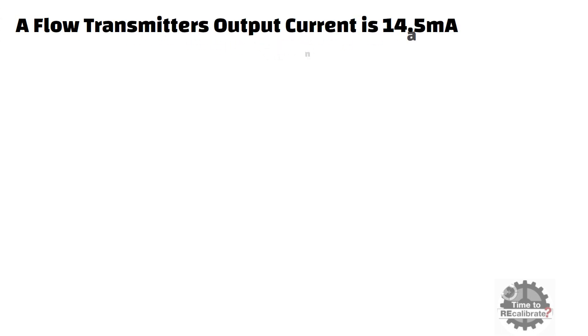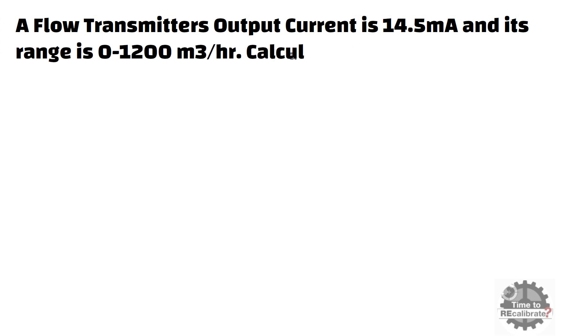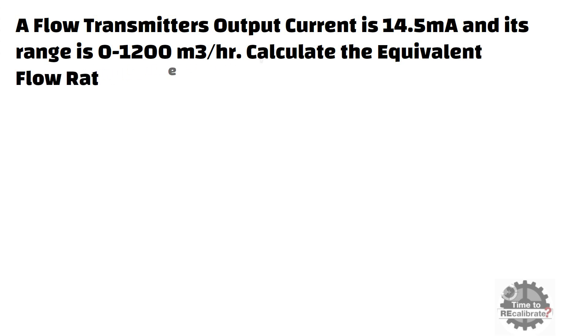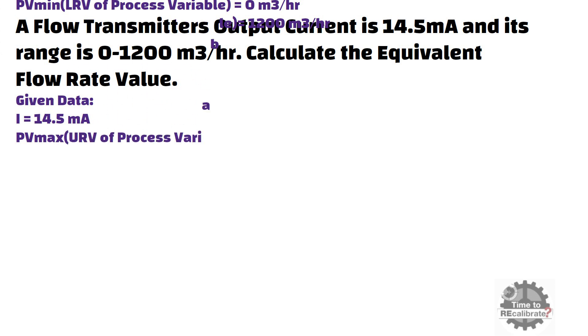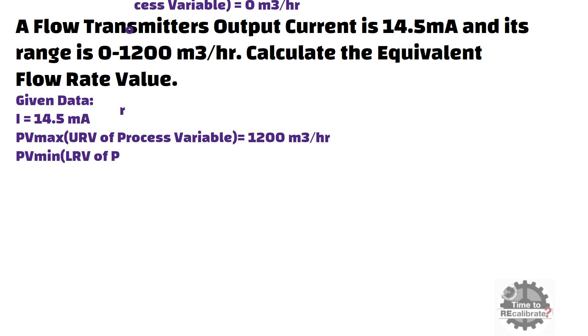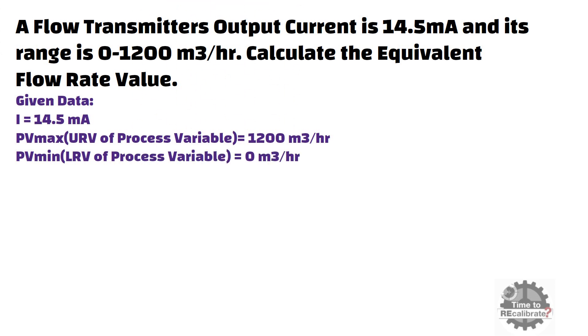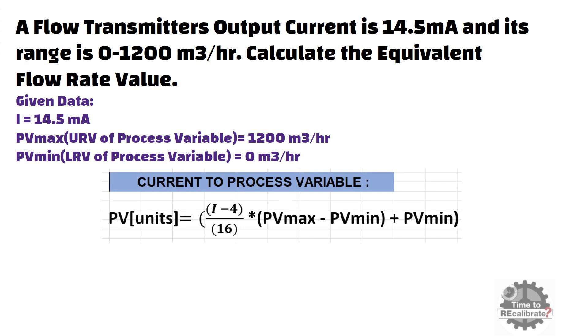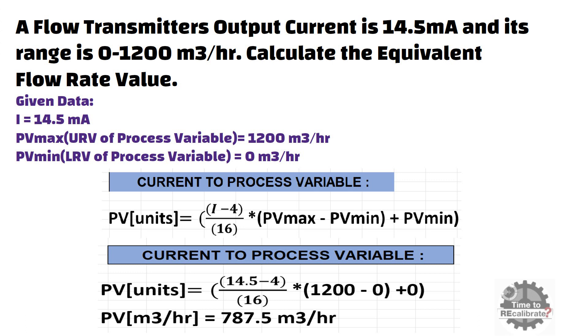A flow transmitter's output current is 14.5 milliamperes, and its range is 0 to 1200 cubic meters per hour. Calculate the equivalent flow rate value. The given data is: I = 14.5 milliamperes, PVmax = 1200 cubic meters per hour, and PVmin = 0 cubic meters per hour. Putting all these values into the equation and doing the math, you will get 787.5 cubic meters per hour. In other words, when current is 14.5 milliamperes, the process variable value is 787.5 m³ per hour.